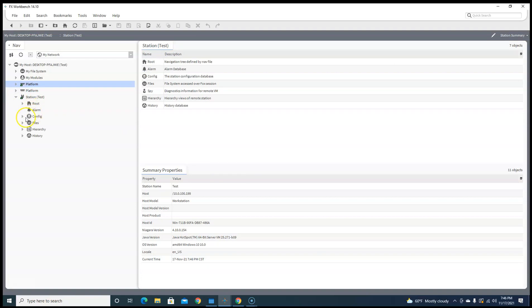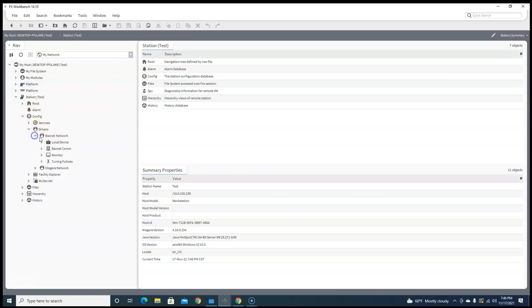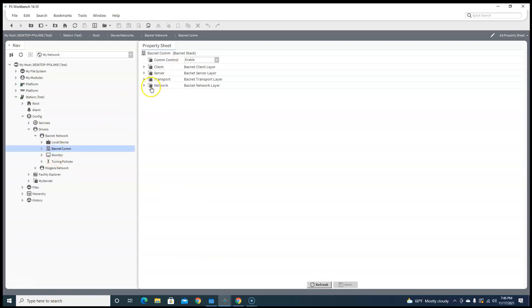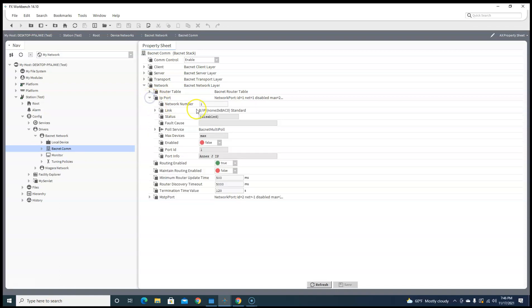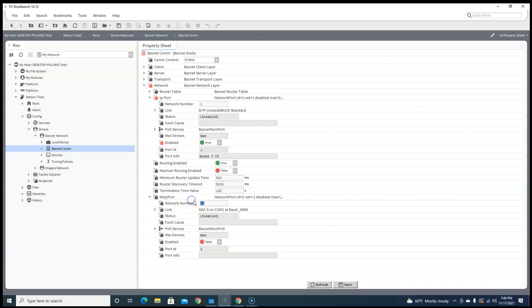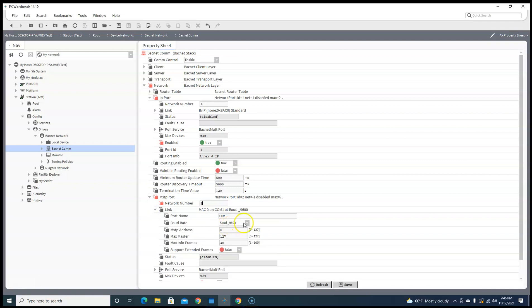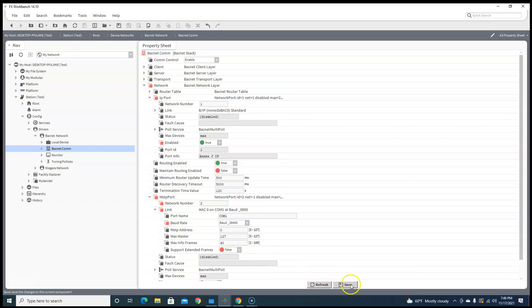Now as you can see in your drivers, you have a BACnet network, you have an IP network - network one, enable that. And then you have an MSTP network, we'll call that network two, and we'll go ahead and set that guy up for 38.4, comm one's good, save.